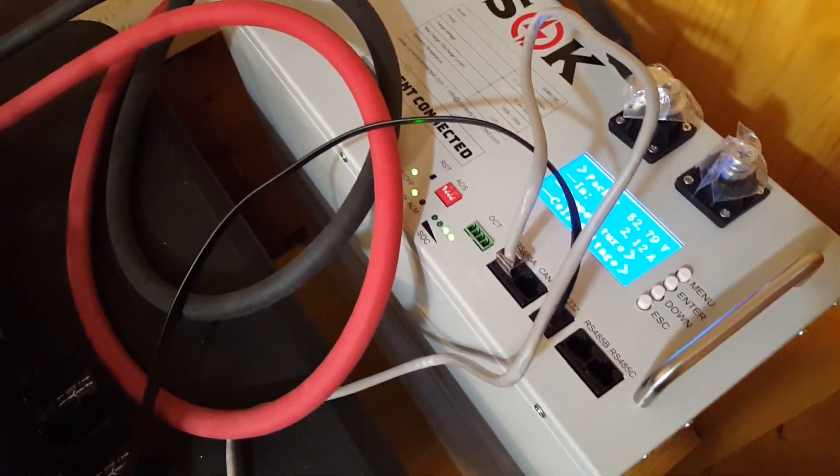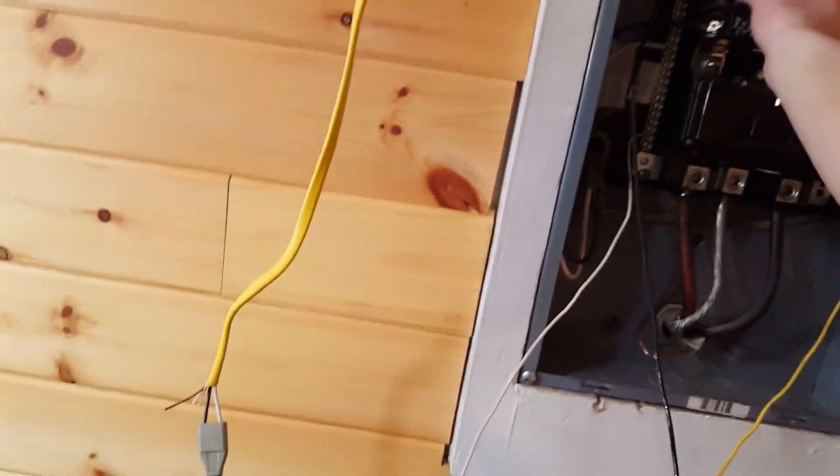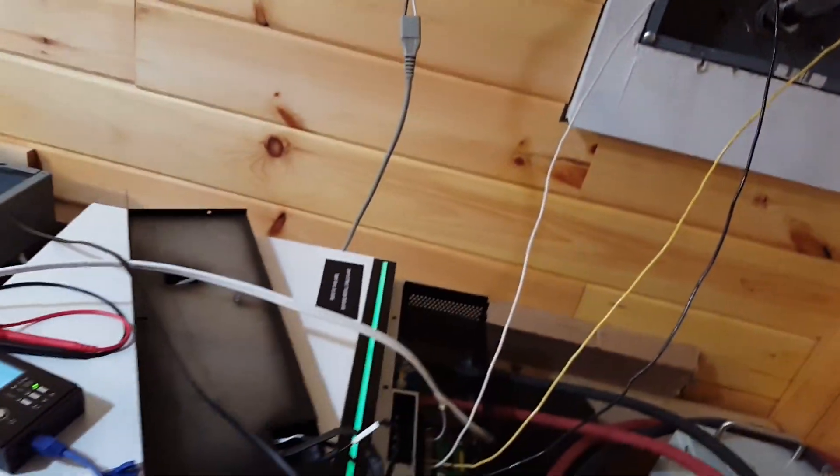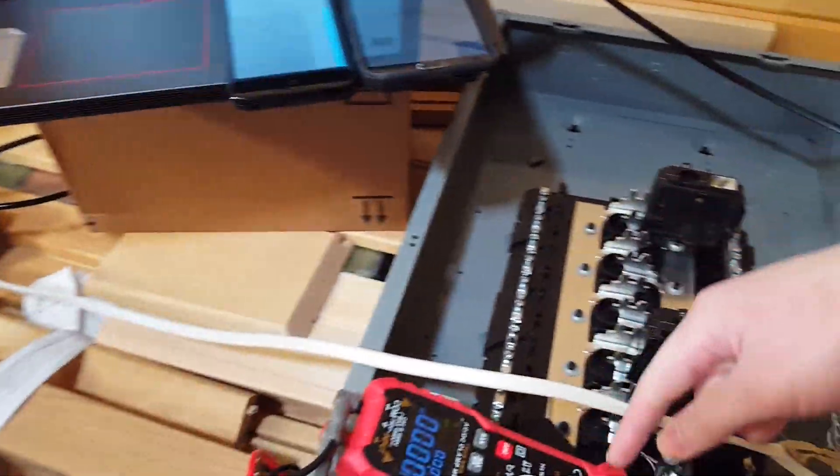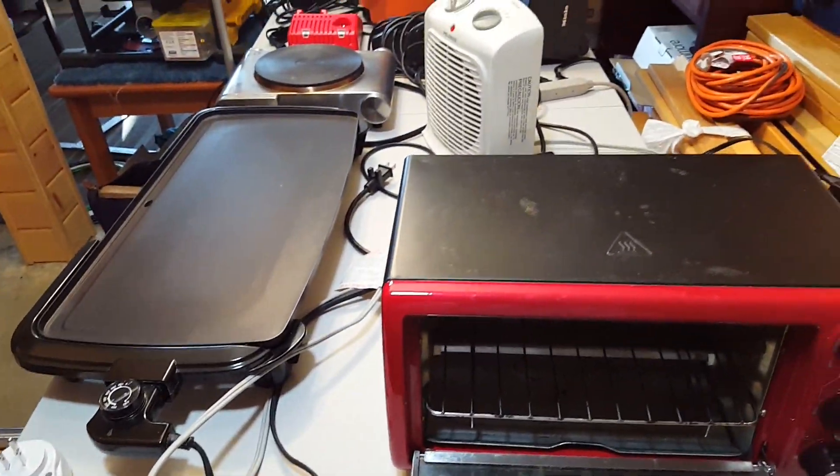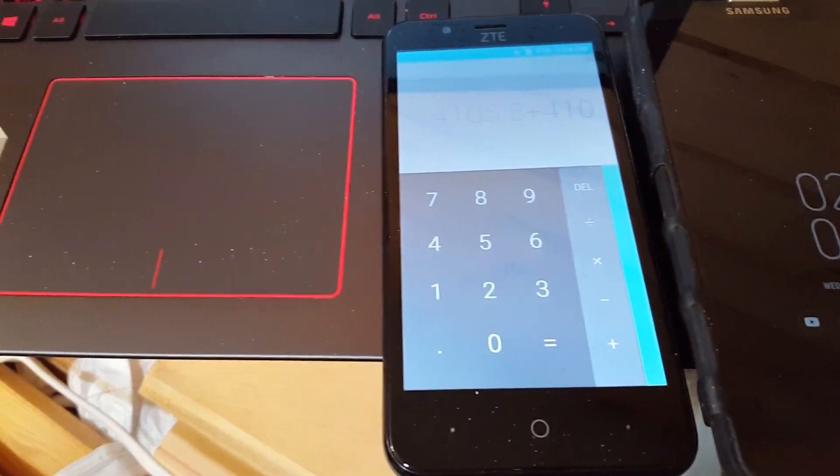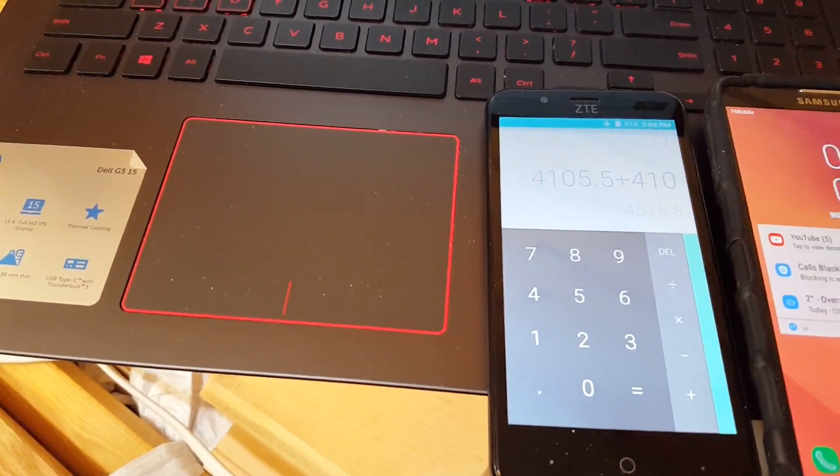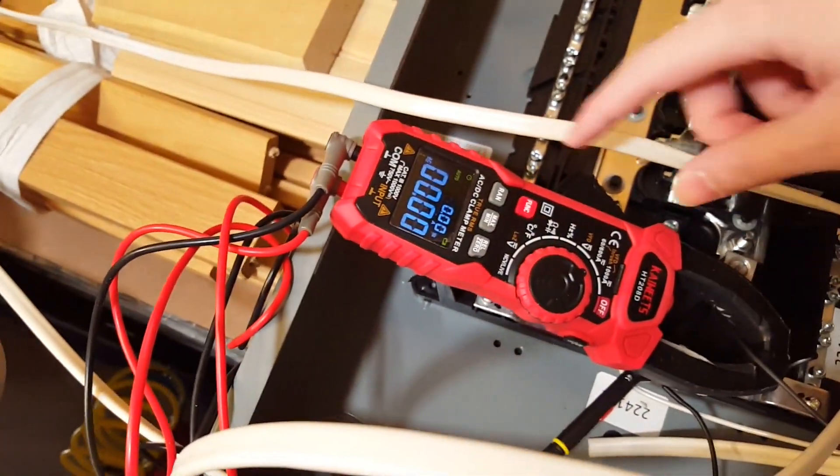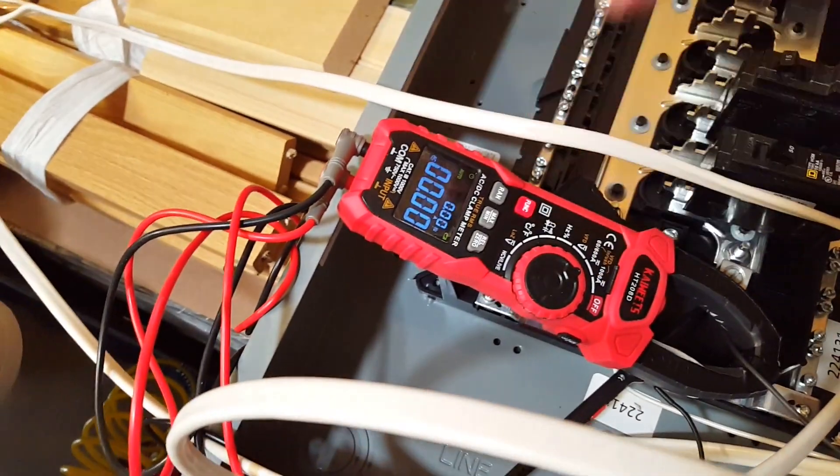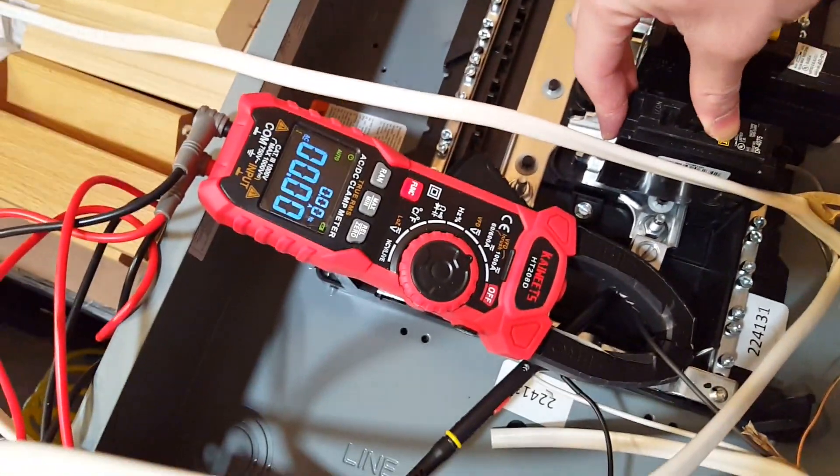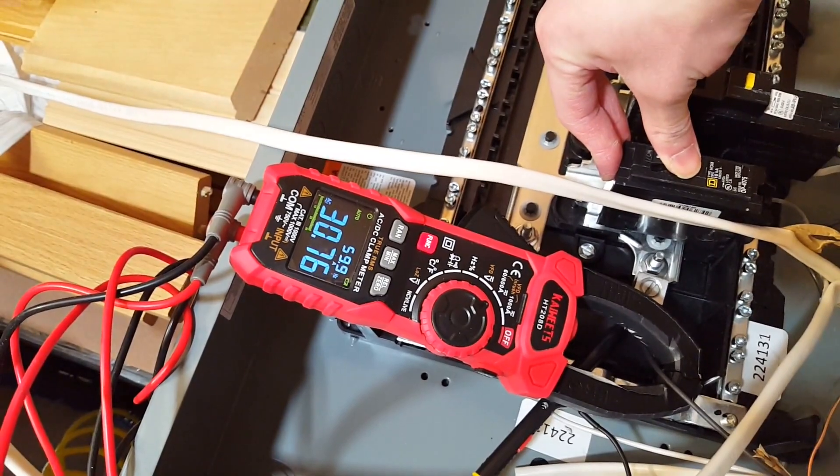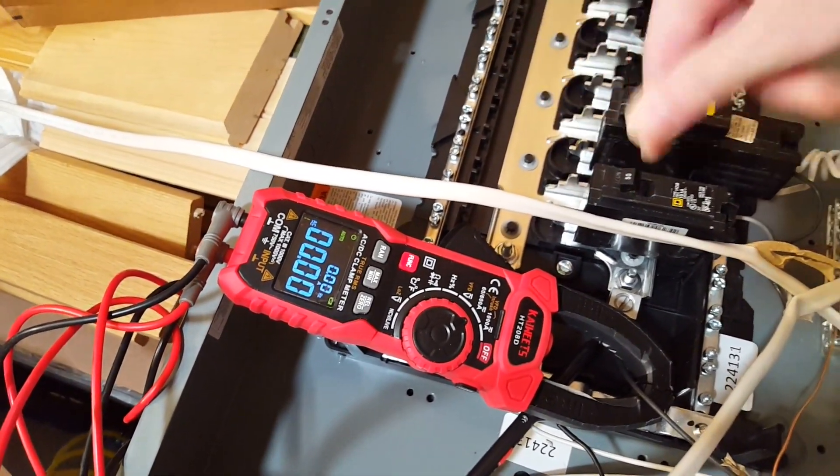Okay. The battery's back from coffee break. It has reconnected with the BMS. So let's try disconnecting from grid first and then we'll switch on the loads and see if we can run these three appliances at a total of 4105 watts. We'll see the AC side. AC amps. Check, turn that on right now. It tried. Again, goes into overcurrent.